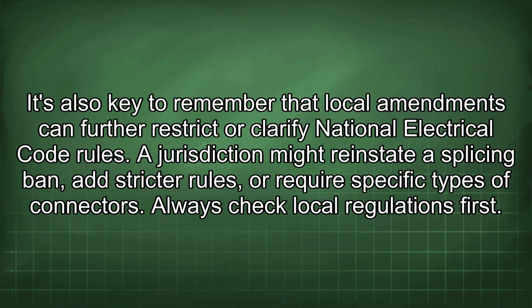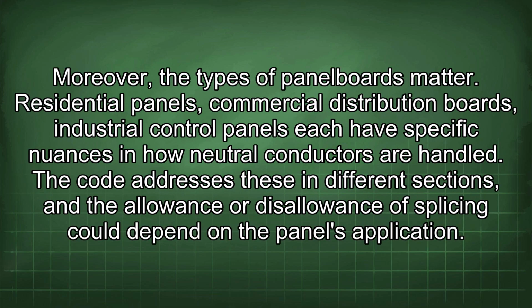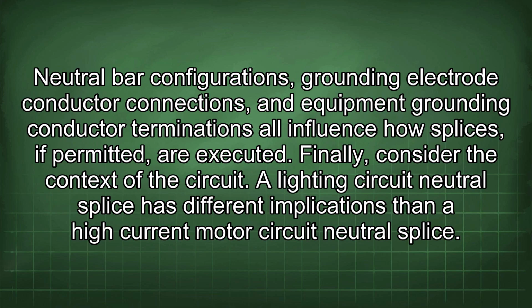It's also key to remember that local amendments can further restrict or clarify National Electrical Code rules. A jurisdiction might reinstate a splicing ban, add stricter rules, or require specific types of connectors. Always check local regulations first. Moreover, the types of panelboards matter. Residential panels, commercial distribution boards, and industrial control panels each have specific nuances in how neutral conductors are handled. The code addresses these in different sections, and the allowance or disallowance of splicing could depend on the panel's application. Neutral bar configurations, grounding electrode conductor connections, and equipment grounding conductor terminations all influence how splices, if permitted, are executed.